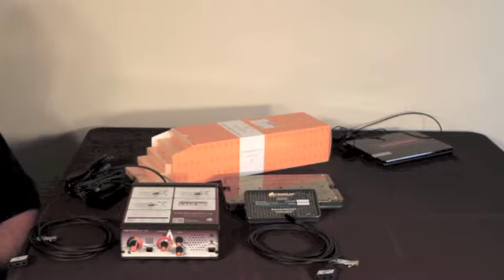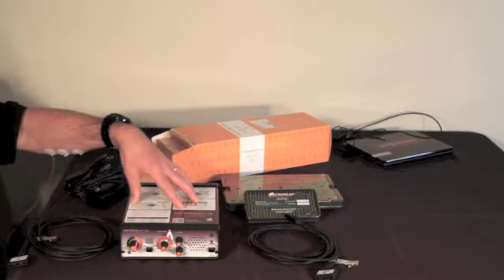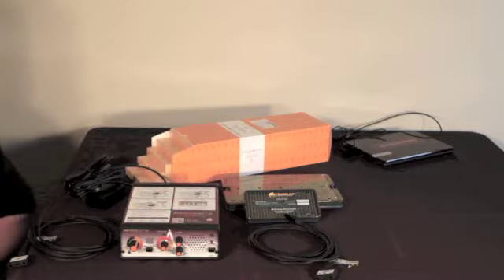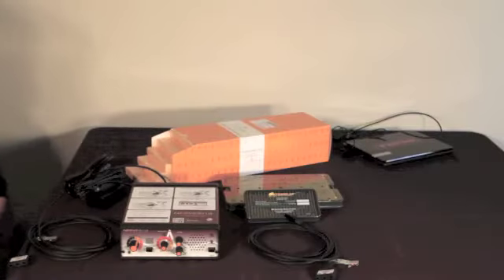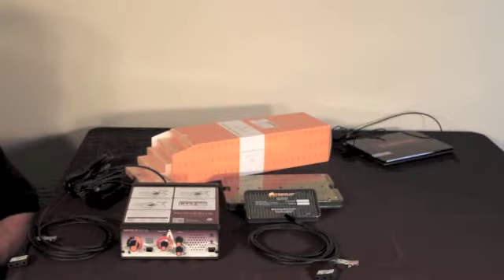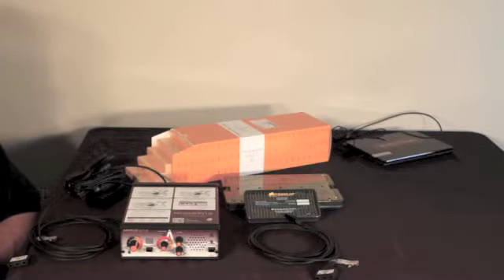Step one is to make sure the Nerveana is charged the night before the surgery. The charge is good for 12 hours of surgery. Number two, once the Nerveana is charged, bring it to the operating room and position it within 6 feet of the patient's head. Make sure to place the Nerveana away from any electrocautery equipment. The electrocautery electrical noise can affect the performance of the Nerveana system.